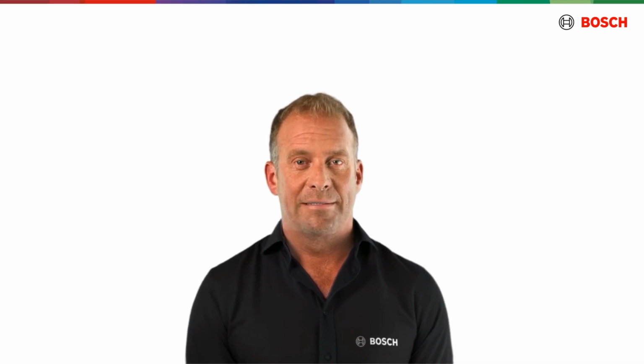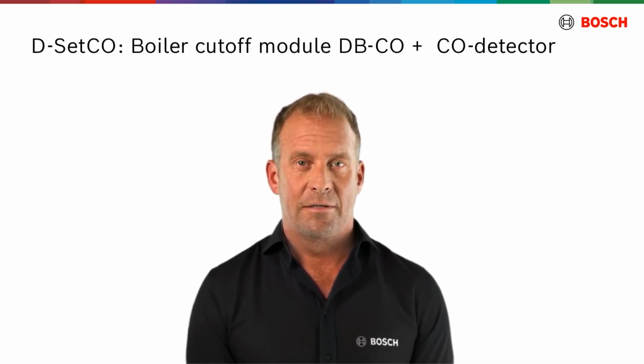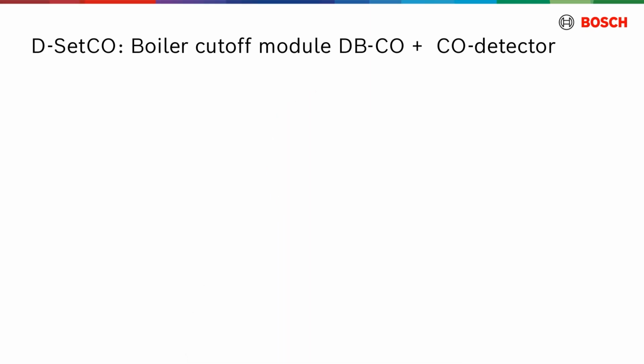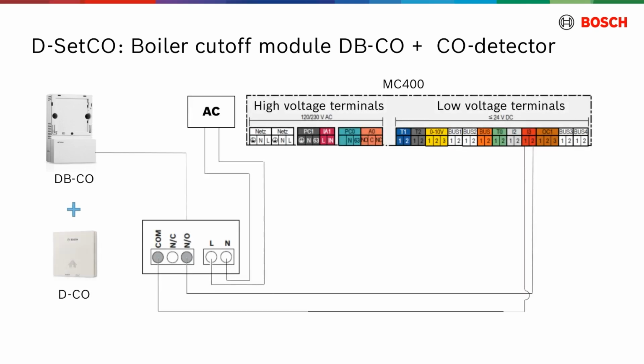For the safe operation of the Bosch boiler cascade with cascaded flue arrangement, it is essential to utilize the CO detector set. This set includes an automatic boiler cutoff module, DBCO, and a CO detector, DCO. The potential free contact of the DBCO automatic boiler cutoff has to be connected to the I3 terminal of the MC400 Cascade module, as shown in the provided diagram.